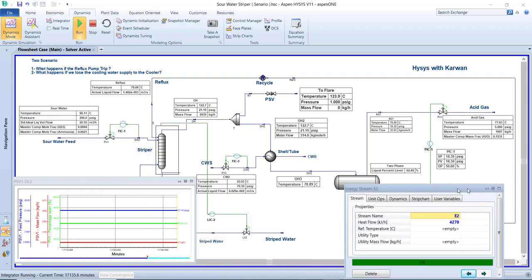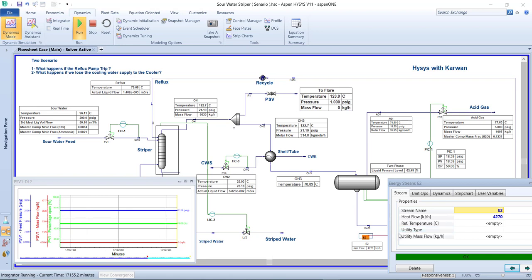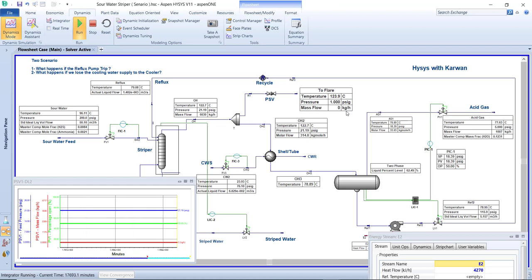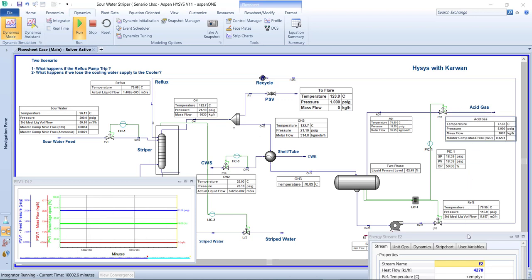Now I want to go to the pump. Look at the heat flow of the pump in kilojoules per hour. When I bring it down to near zero, that means the pump is shutting down. This is the scenario — what happens if the reflux pump trips. I'm monitoring the tower pressure, the PSV mass flow rate, the top temperature, and the position of the pressure indicator controller (PIC).